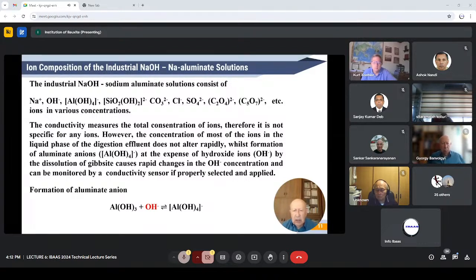The conductivity meters measure the total concentration of ions, therefore it is not specific for any particular ions. However, the concentration of most of the ions in the liquid phase of the digestion effluent does not alter rapidly, whilst formation of aluminate anions at the expense of hydroxide ions by the dissolution of gibbsite causes rapid changes in the hydroxide ion concentration and can be monitored by a conductivity sensor if it is properly selected and applied. Here is the well-known equation of the formation of aluminate anion from gibbsite and hydroxide ions.